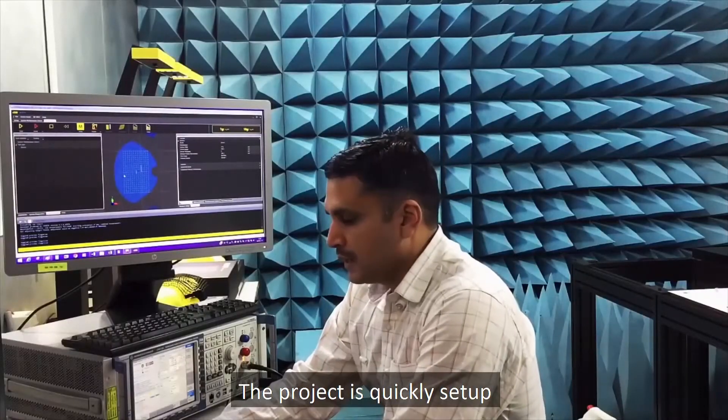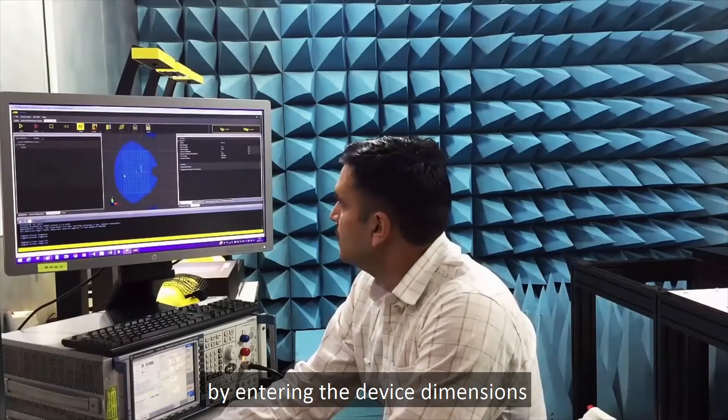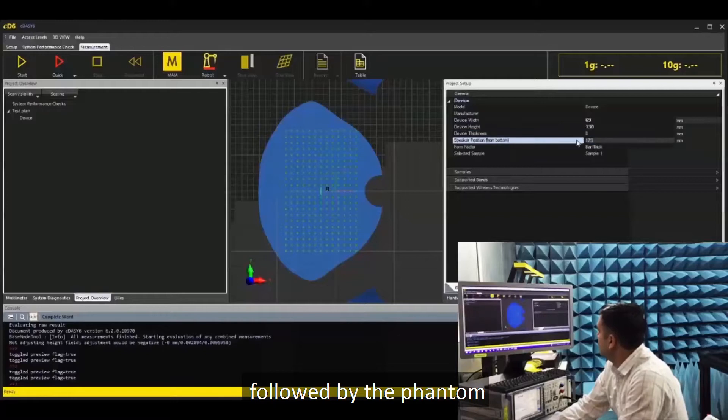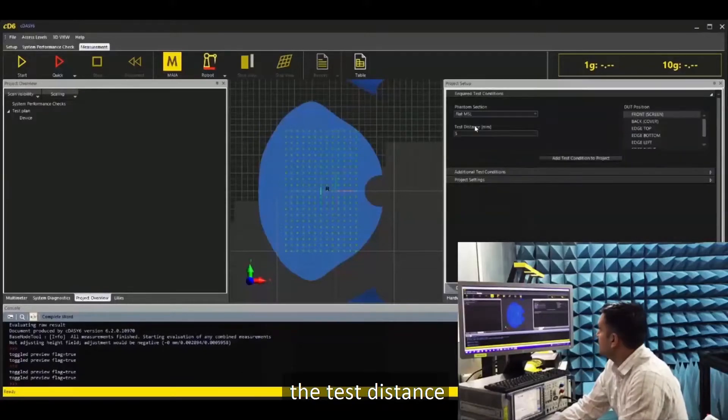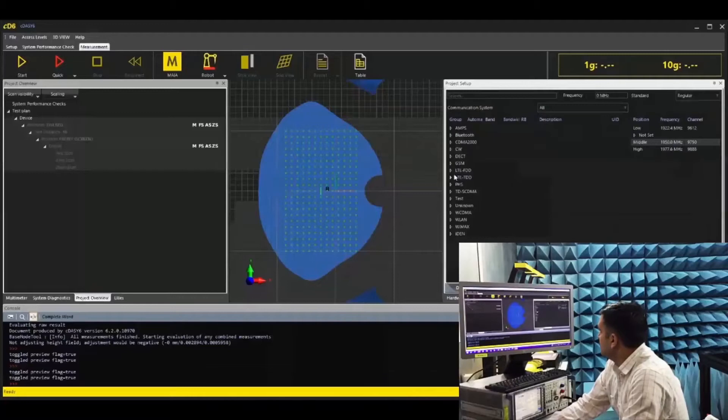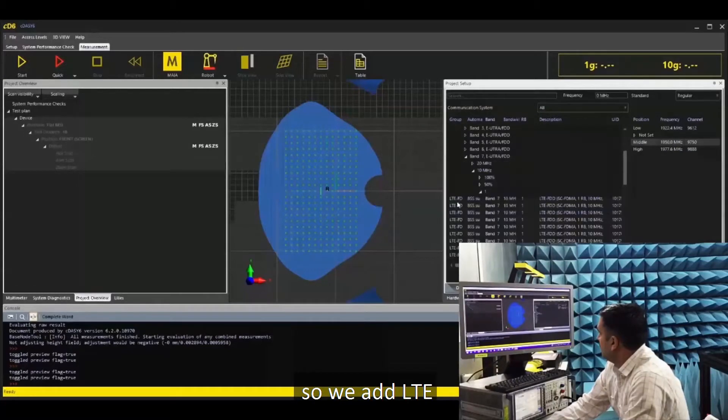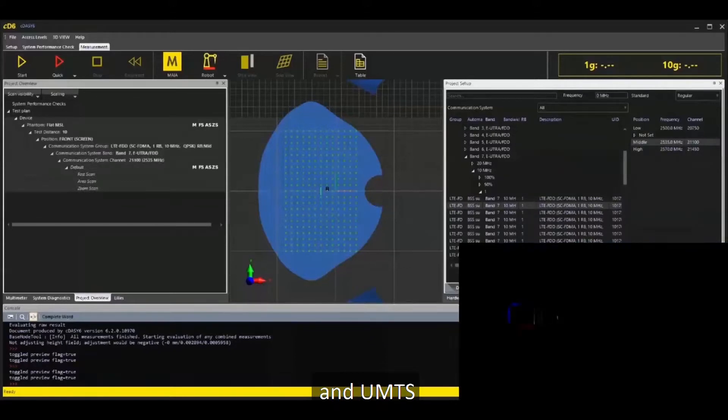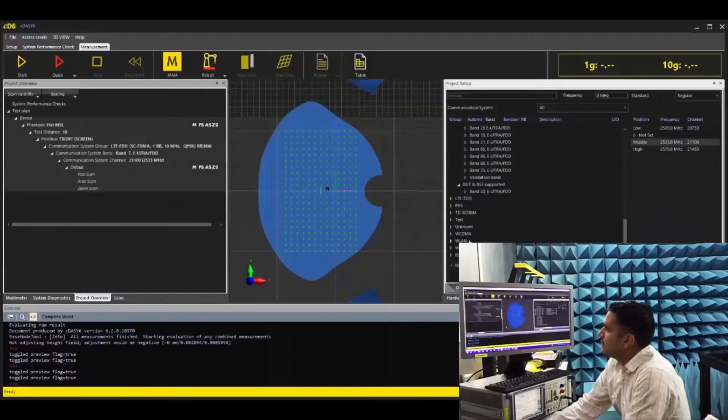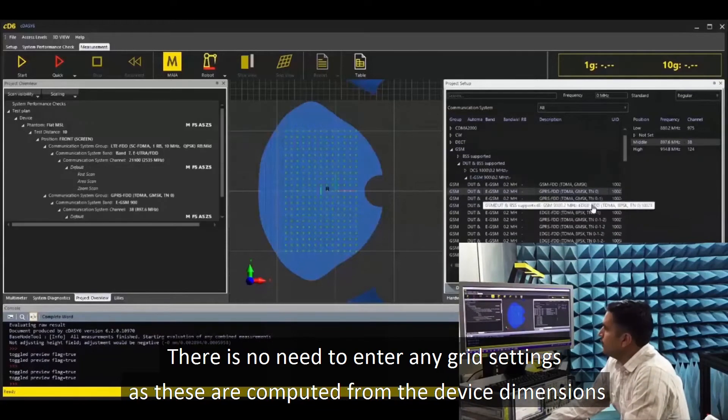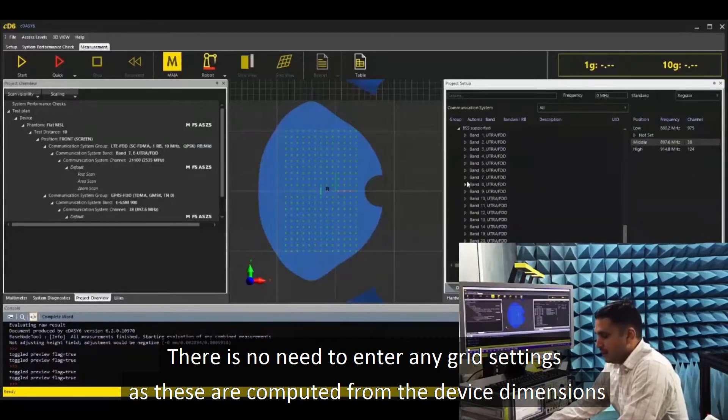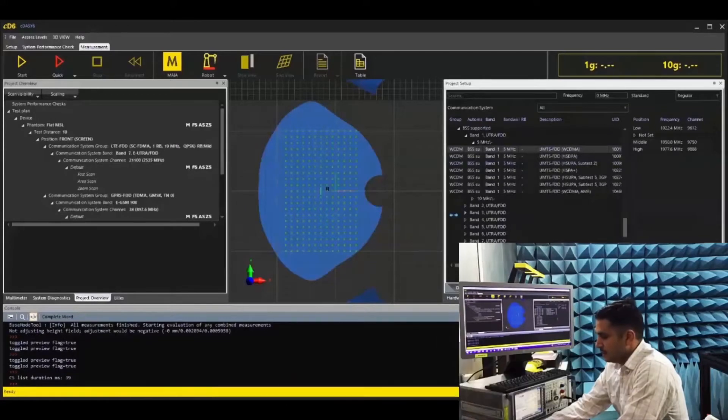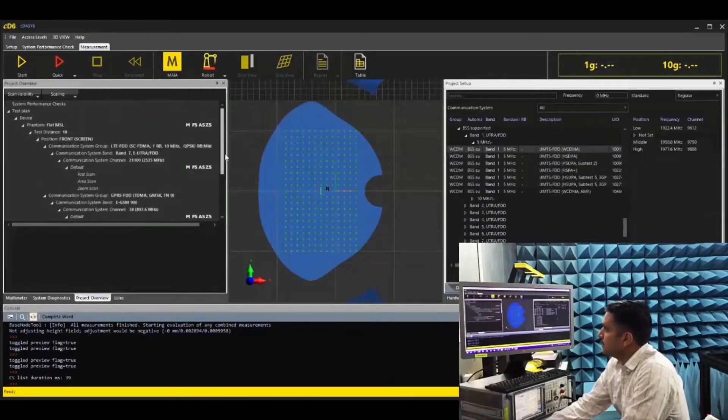The project is quickly set up by entering the device dimensions followed by the phantom and test distance and the communication systems. So we add LTE followed by GSM and WCDMA. No need to enter any grid settings as these are computed on the device dimensions, frequency, and the test distance.